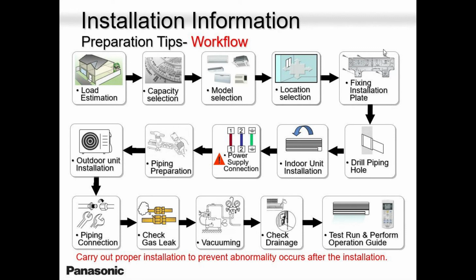Let's talk a little bit about the installation that we want you to do and things that we don't want you to do. Okay? Obviously, somebody is going to do some load calculation. I know guys nowadays, they just walk into a house, they look around, they come up with a solution. Oh, 12,000 BTU is fine. 18,000 BTU is fine. No, it's important to do a load calculation. Once you do your load calculation, you pick a capacity, you pick a model, you pick a location, and now you start to do your job.